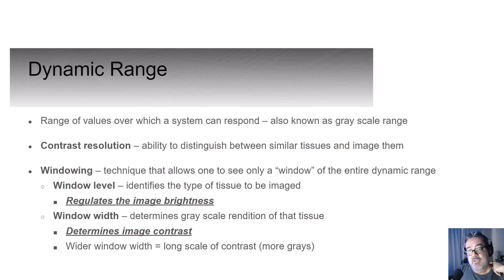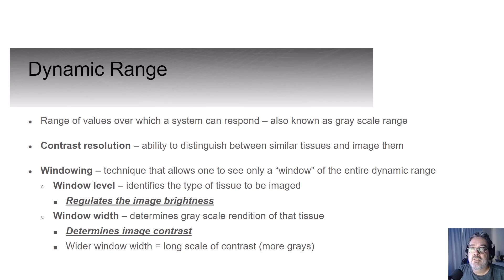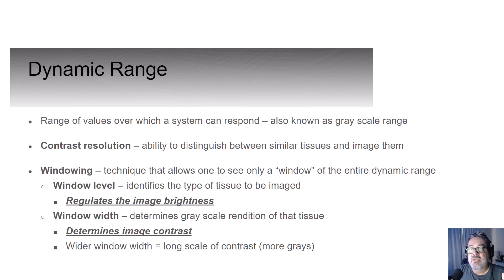Let's talk a little more about dynamic range. This is the range of values over which a system can respond, also known as the grayscale range. This includes hardware like the monitor and the computer, and it also includes the software. Contrast resolution is the ability to distinguish between similar tissues. The computer's ability to enhance visualization and tissue differences is going to be so much greater if you're providing it with optimum technique in the initial data set. When people say they're just going to window an image, they mean they only want to see a window or a portion of the entire dynamic range.